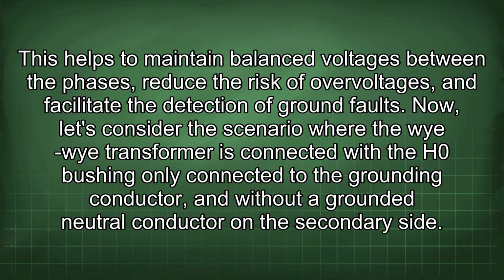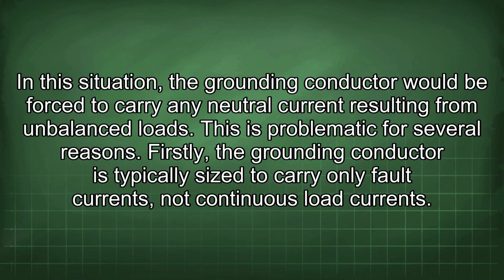Now, let's consider the scenario where the Wye-Wye transformer is connected with the H0 bushing only connected to the grounding conductor, and without a grounded neutral conductor on the secondary side. In this situation, the grounding conductor would be forced to carry any neutral current resulting from unbalanced loads. This is problematic for several reasons.